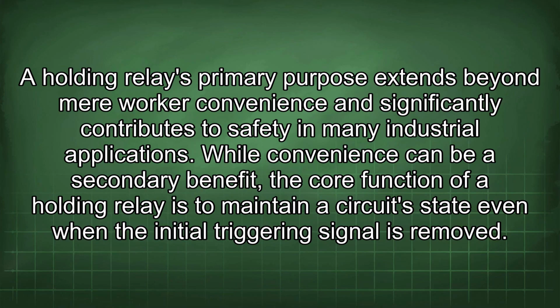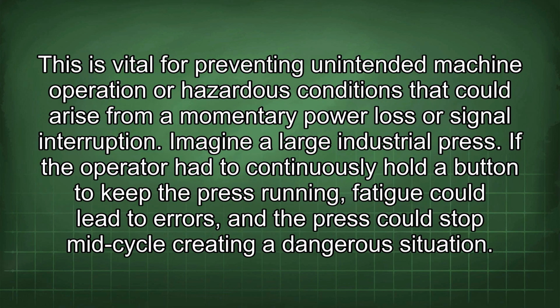Holding relays' primary purpose extends beyond mere worker convenience and significantly contributes to safety in many industrial applications. While convenience can be a secondary benefit, the core function of a holding relay is to maintain a circuit state even when the initial triggering signal is removed. This is vital for preventing unintended machine operation or hazardous conditions that could arise from a momentary power loss or signal interruption. Imagine a large industrial press.